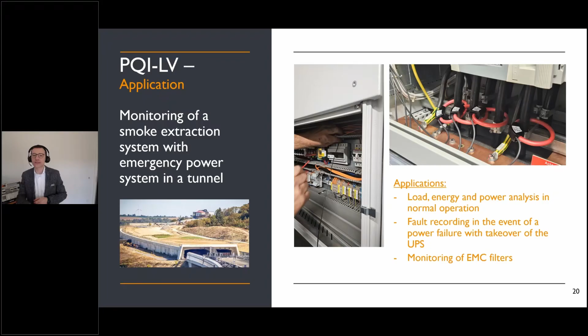Here you can also see the opportunity of Rogowski coils. We still deliver these Rogowski coils with the device, and the installation is very easy. The good thing is that the Rogowski coils are also able to monitor the supraharmonics of the current in a really good way, due to the physical principle of a Rogowski coil. If you choose other current sensor technologies, it can happen that the supraharmonics cannot be measured with the accuracy you want.